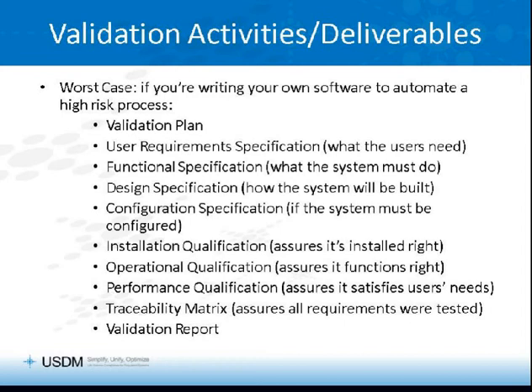And we're not done yet. Once we've conducted our testing or written our tests, we need to develop a traceability matrix. And this simply ties every user requirement to one or more tests so that we prove we've gotten full test coverage. We prove that every requirement has been tested to assure that it's been met.